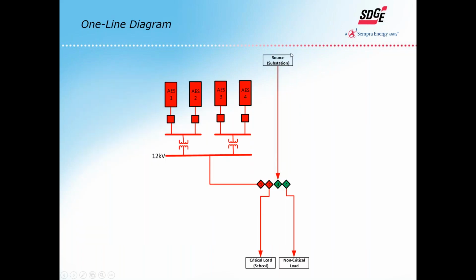That allows us to electrically isolate our energy storage system and our critical load at the school from the source, which is the substation and SDG&E's grid, and from any non-critical loads not within our island. So this whole portion on the left, the energy storage and the critical load, if we lose the grid and have an outage, this is what will remain energized.